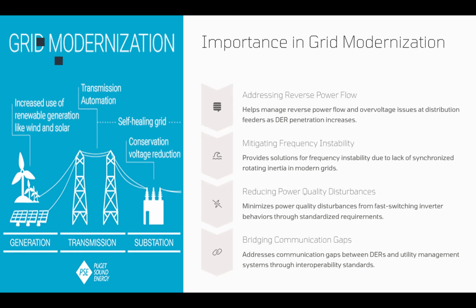Now, the last aspect is that when we talk about distributed resources, we are talking about thousands of small resources that are everywhere in our grid, and the utility owners and the control system should deal with all of them and coordinate all of them. So that means we need a proper communication system, so we could actually control, manage, and coordinate those distributed resources. We have to have remote access to adjust the DER settings, so utilities can make sure they respond effectively when there is a grid emergency, or coordinate DER dispatch for demand response.